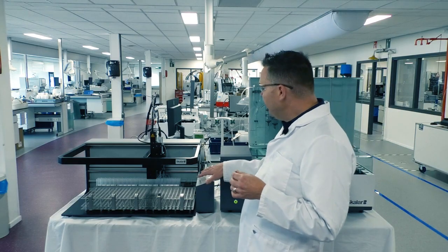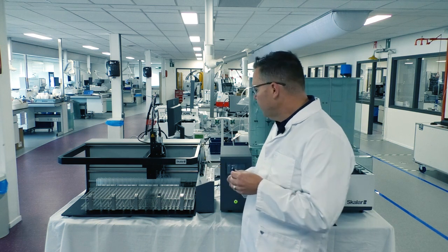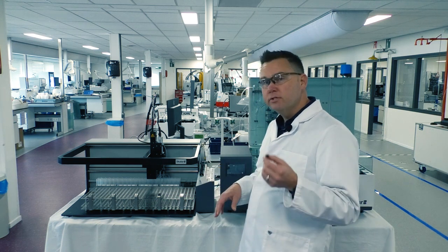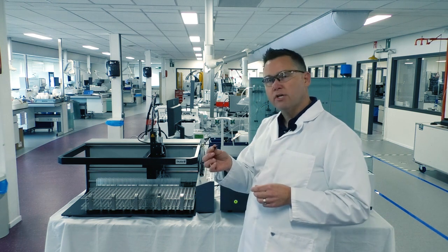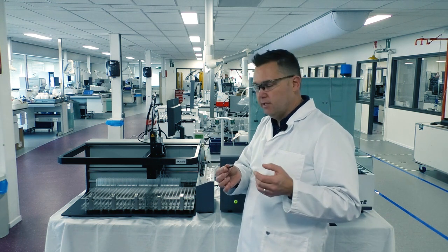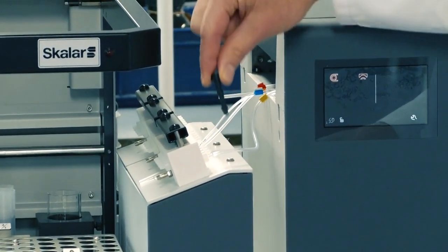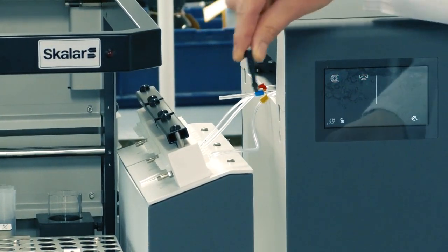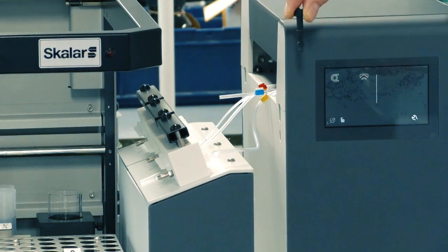They're mainly maintenance free. So once a year we recommend, on your PM visit by a Skalar engineer, or users can do it themselves, you remove the tops of these valves, and these little plungers come out, and there's a series of O-rings that we replace annually to make sure that they're sealing really well as they slide. Because in essence, if you can visualize, they're just pulling these rinse valves up and down to divert the flow from reagent to DI water to rinse the system out, and then vice versa.